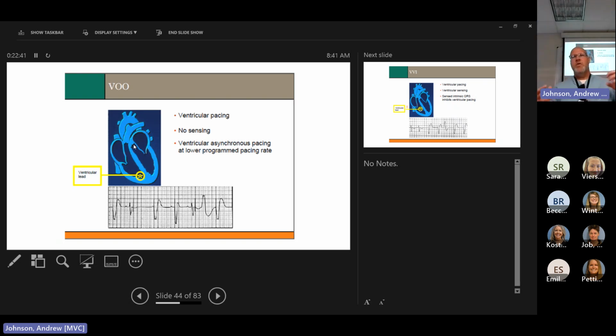So VOO, DOO, basically we're blinding the pacemaker. We're saying, I don't care what I see, I am pacing. So I'm not looking for anything, and it is, say, VOO at 60 beats a minute. You will see a pacing spike at 60 beats a minute regardless. Now, does it capture or not capture? If you had your own intrinsic conduction that came through, your heart is squeezed, and I throw a pacing spike right now as it's squeezed, that pacemaker's not going to make it squeeze again. You can't squeeze something that's already squeezed. That's a functional loss of capture, and that's completely okay.